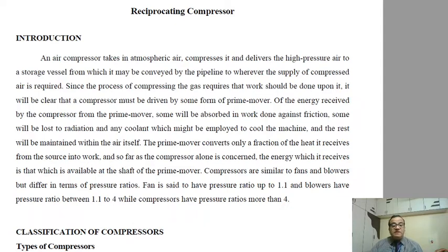Compressors are similar to fans and blowers but differ in terms of pressure ratio. A fan has a pressure ratio up to 1.1, blowers have a pressure ratio of 1.1 to 4, while compressors have a pressure ratio of more than 4.